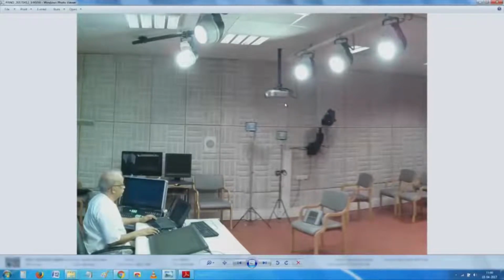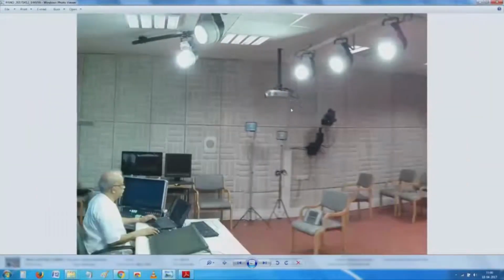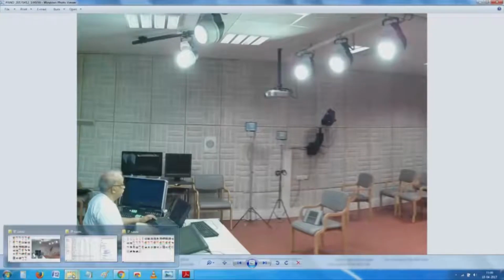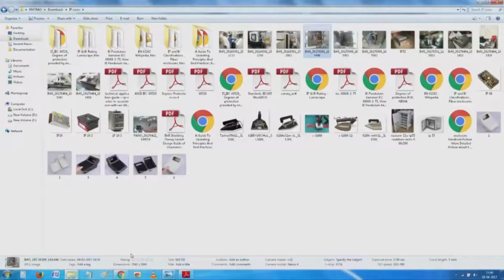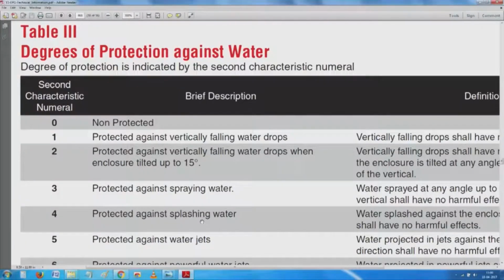Chances are, when this cold air from it meets any moist air, condensation can take place, and this condensation can affect equipment like this. You have seen here, we have a projector here. So, chances are it will get affected. I will see if I have one more slide. No, it is the same slides everywhere. I will have to go back to this. So, we see here an absolutely unprotected device can get affected even indoors because of unintended condensation, because of the change in humidity in the environment.